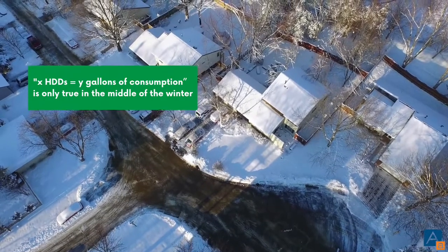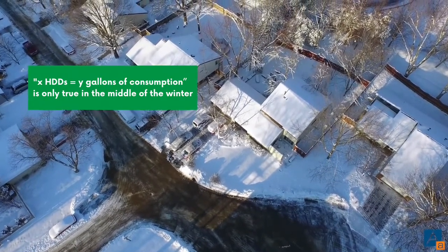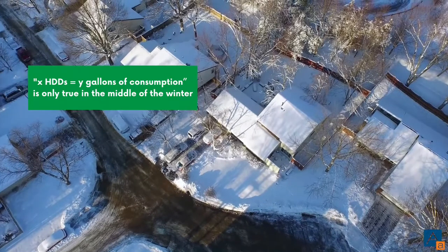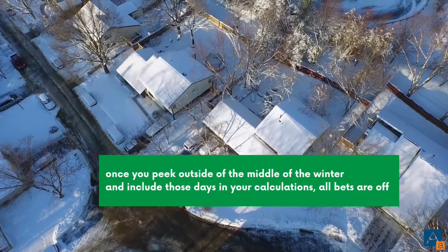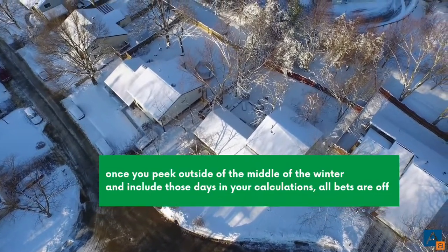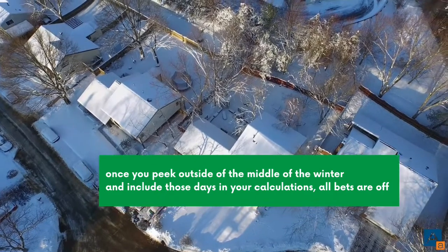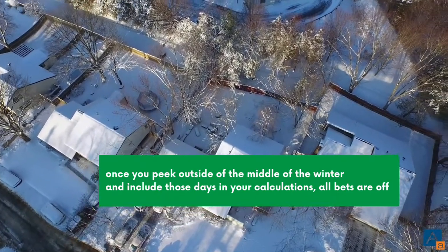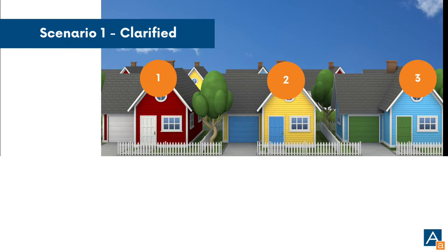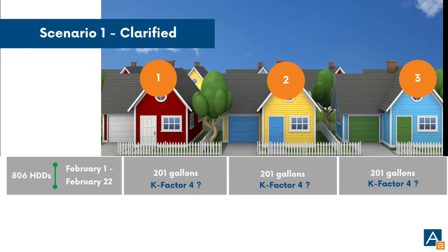If the heating system is on for the entire period in between deliveries, then a true K can be calculated. However, once you peek outside the middle of the winter and include those days in your calculations, all bets are off. Let's try to answer some of these mysteries. Scenario 1 looks like three houses that have Ks of 4, 806 heating degree days, and 200 gallons of consumption. Pretty straightforward. So what happened during the next 800 heating degree days? Shouldn't there have been about 200 more gallons worth of consumption?